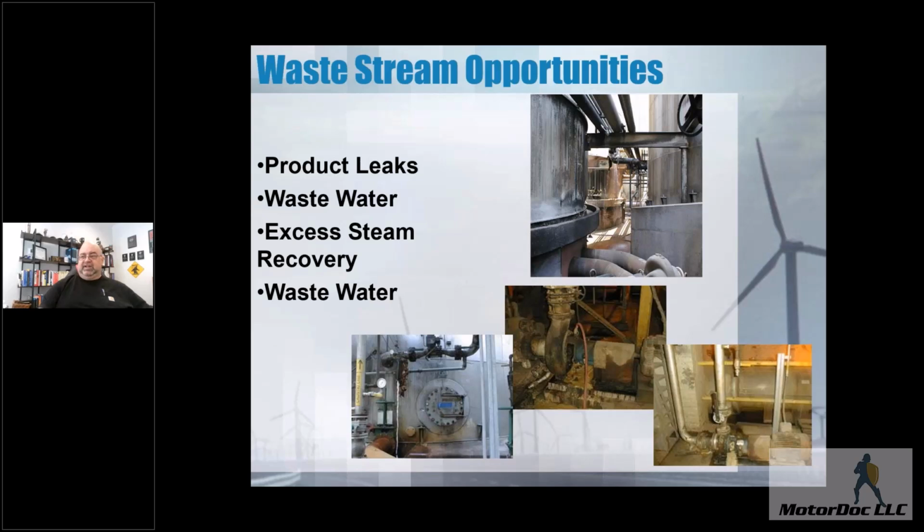So basically, they're putting stuff through waste processing, causing that side to work even harder. We had actually put that together, and a majority of their process involves pumps. And in the mash side, that came out to be about 15% of their electrical energy consumption. And then when it hit the wastewater treatment plant, it actually doubled the consumption there.